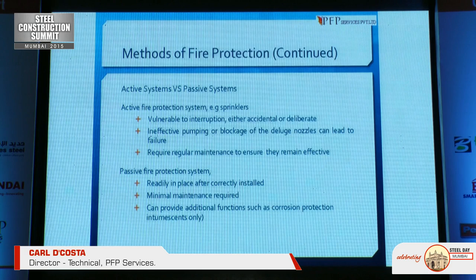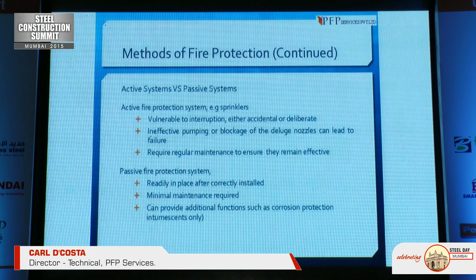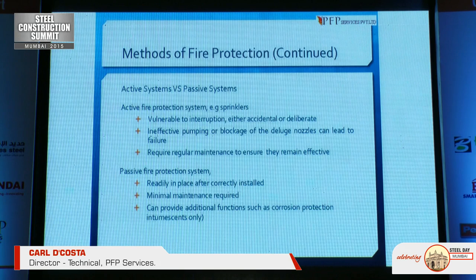Regarding active systems versus passive systems: some consultants think that if we have an active system, we don't need any protection to the steel. However, active fire protection systems like sprinklers are vulnerable to interruption from electricity outage or insufficient water in storage tanks — whether accidental or sometimes deliberate. There can also be ineffective pumping or blockage of the deluge nozzles. In India, fire safety maintenance is poor, so when a fire occurs, sprinklers may already be clogged with dirt and simply don't work.